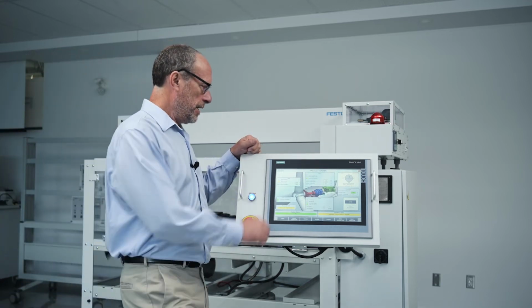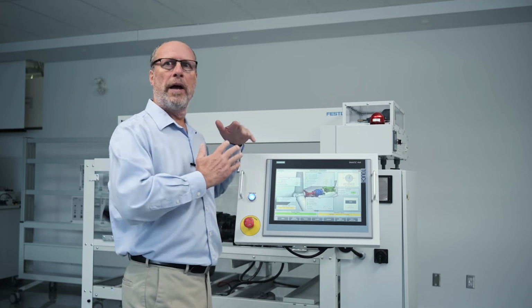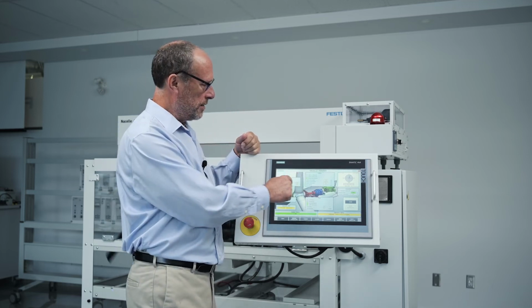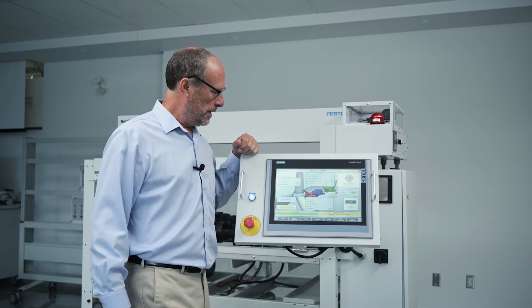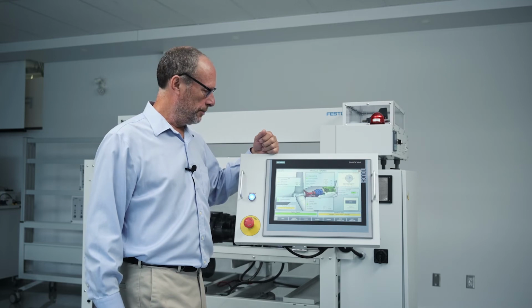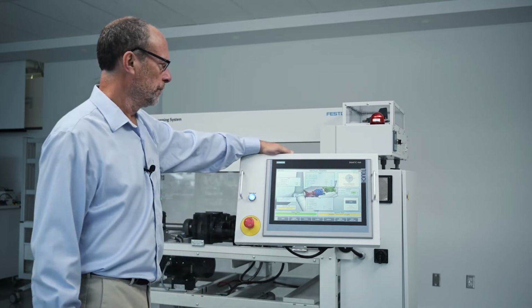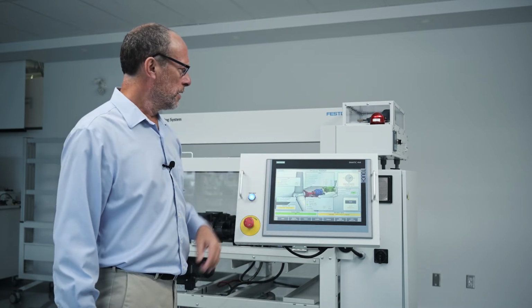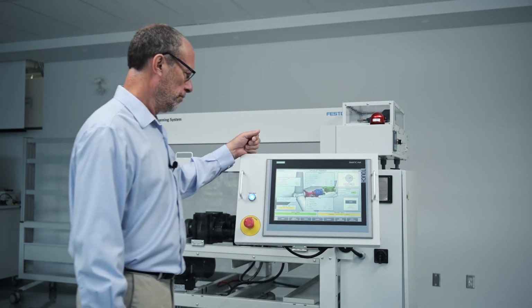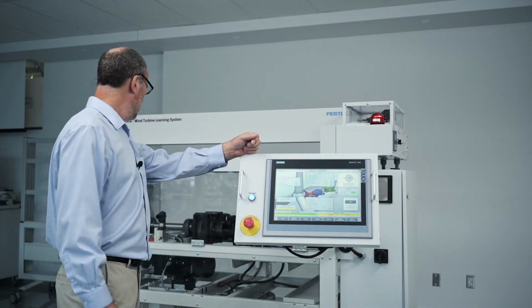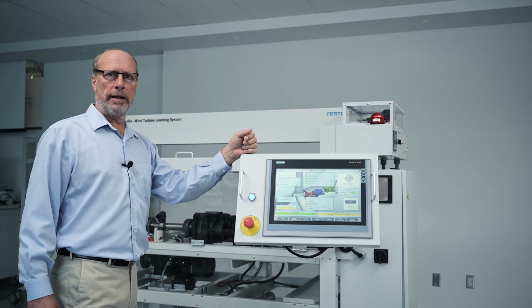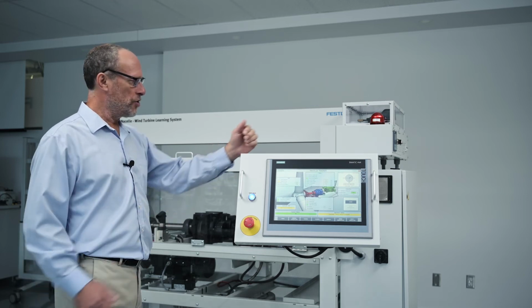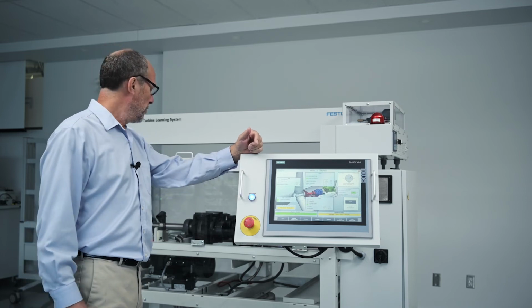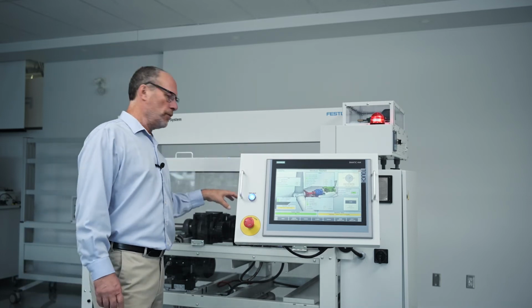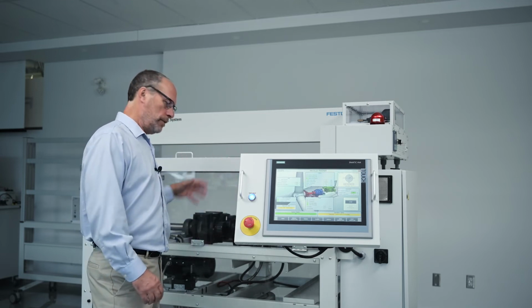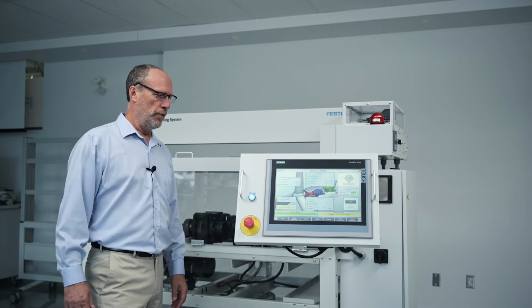And here we simulate the pitch of the blades according to wind condition. You actually can see that the pitch will change to maintain synchronization. You see here the correction coming here. So all this can be done in a classroom environment. Of course, it's a big machine, some noise, but not so bad. We can live with this. And you can hear the hydraulic pump going in and out to maintain a working pressure of the system.